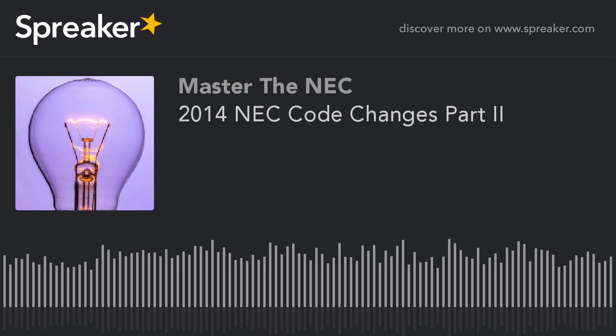Next, let's look at some of the other areas that changed in 210.12(A) for arc fault circuit interrupters. Two new locations were added to the list that require AFCI protection. I know that's going to make the AFCI people real happy. It's the kitchens and laundry areas. So you have the GFCI requirements that have been expanded to the laundry area. Now you have the AFCI that's expanded to the kitchen and laundry area. And again, the kitchen, that's going to apply to the small appliance branch circuit.